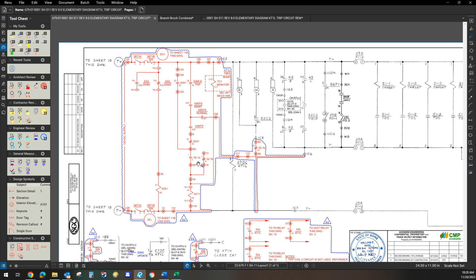43, 52, 63 - I can tell you that a 52 is an AC breaker, a 43 is a switch, and a 63 is a pressure switch. How do I know that? Because of the IEEE device numbers. If you look, 43 says manual transfer selector switch, 52 is an AC circuit breaker, and 63 is a pressure switch.